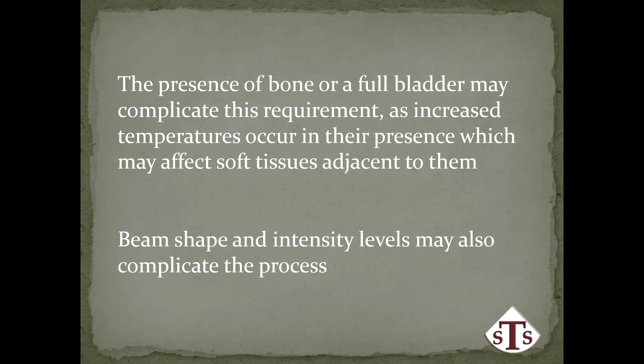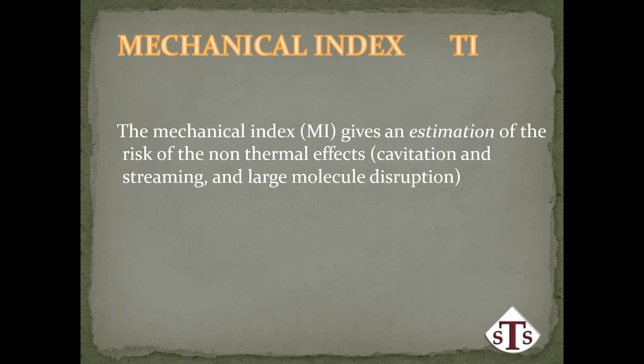So the mechanical index gives an estimation, not an absolute, an estimation of the risk of the non-thermal effects, which is cavitation, microstreaming, and large molecule disruption. And this is the only society that I've found that actually gives values that we can work with when we are scanning to try and limit any potential, and I keep using that word, potential for harm from our scanning.